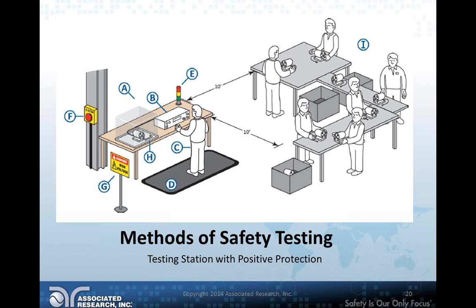And you can see the enclosure is directly linked to the high pot unit. It should be in such a way that the high pot unit is what we call interlocked. Most high pot testers nowadays have an interlock built in. In other words, you can wire it in such a way that if that enclosure door opens, your high pot test will not start or will cease outputting voltage mid-test. Basically, you have to have that door closed in order for the test to be run. That ensures, number one, that the operator can't touch the DUT while it's testing, and number two, should somebody accidentally bump an enclosure door or open it up to where there could be a live exposed conductor or a live DUT while there's a high pot test happening, the high pot test immediately stops and automatically discharges the unit under test.